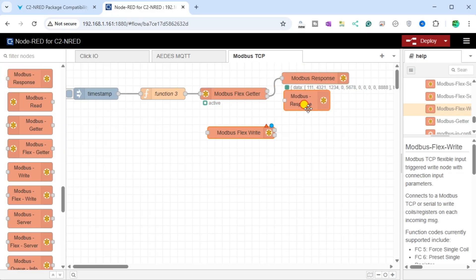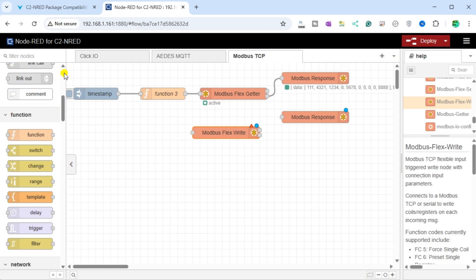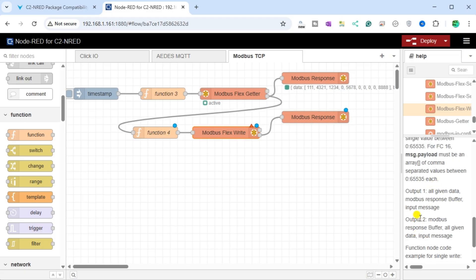We will now set up the C2NRED Modbus TCP flow to write to the Click PLUS PLC. Returning to our flow program, add a Function node, a Modbus FlexWrite node, and another Modbus Response node. Join the Modbus FlexGetter node to the new Function node, then the new Function node to the Modbus FlexWrite, then join the Modbus FlexWrite to the Modbus Response node. Under the Help menu for the Modbus FlexWrite, copy the Multiple Write example.